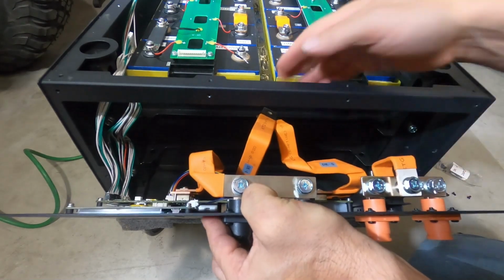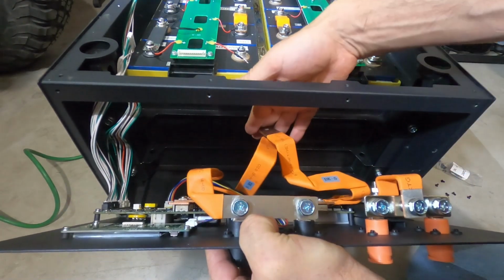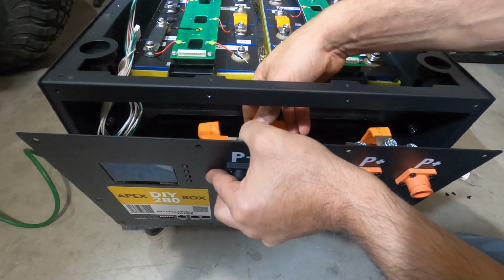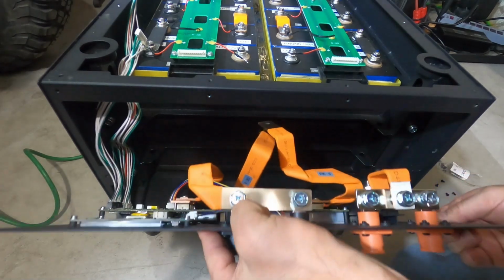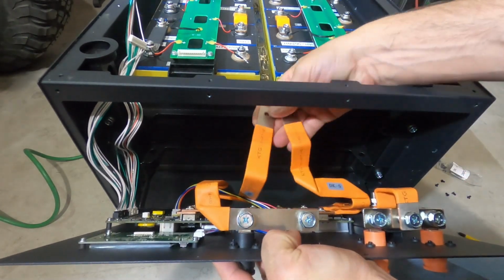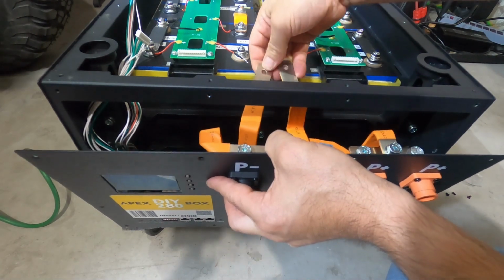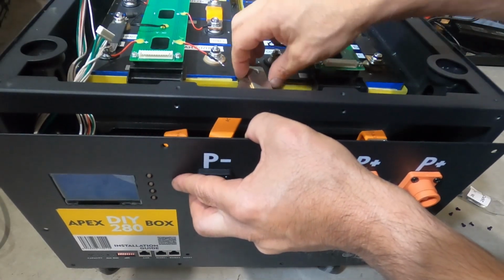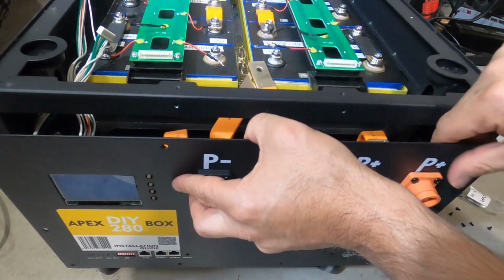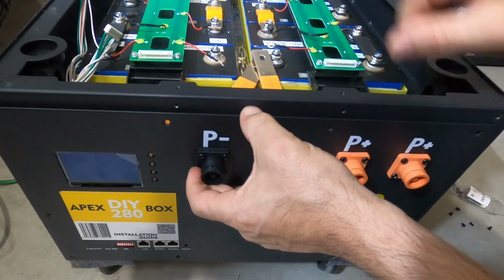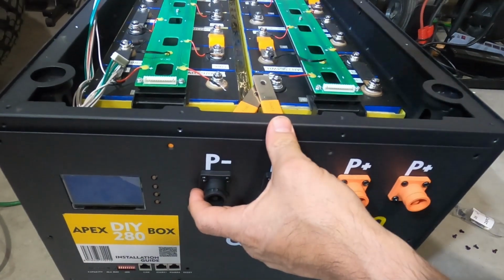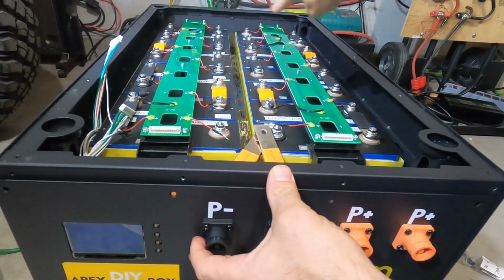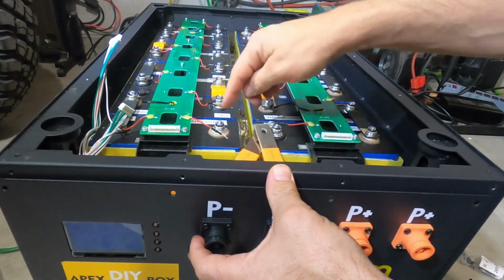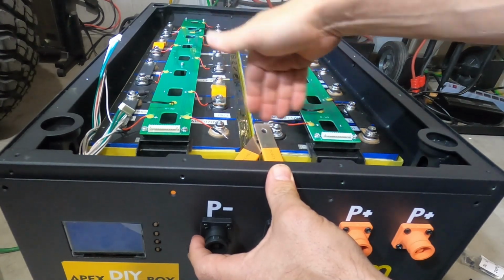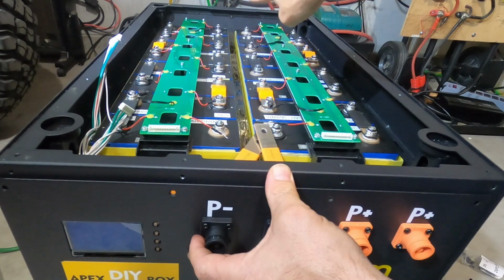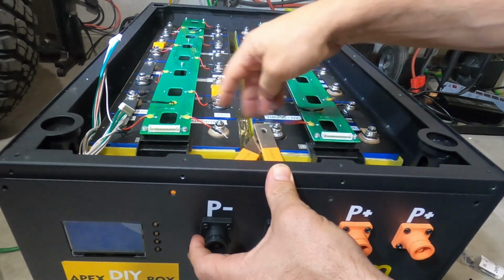When I was putting the screws on, I had gotten the main terminal connectors down here, and when I closed it, they were jammed in there and I couldn't get them up. So when you put it together, make sure these come above the cells. But be careful not to short these two, because then you'll create a short, which is the reason why I have the bus bar in the back disconnected. So if you touched these with no voltage here, there would not be a short. But if you had that bus bar connected in the back, this would be live, and if you shorted these two, it would not be nice.